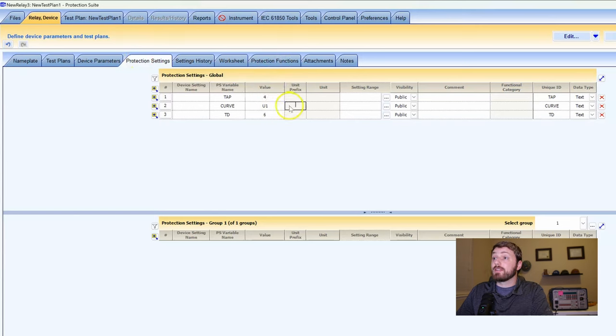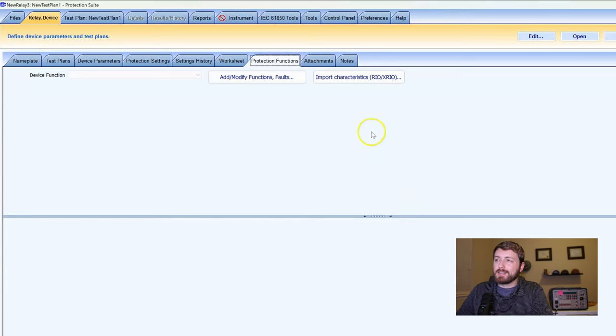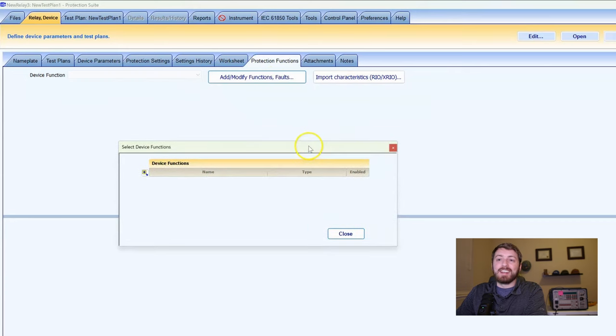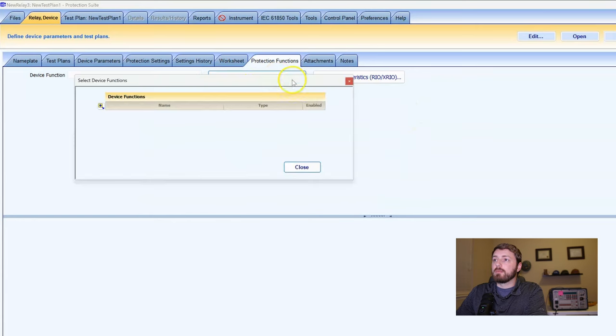Now that I've got my curve settings in, we're going to click on protection functions, and we'll see here that it's blank — it's more clicks than it needs to be. We click 'add/modify functions' and we're going to do overcurrent. This makes life easier.